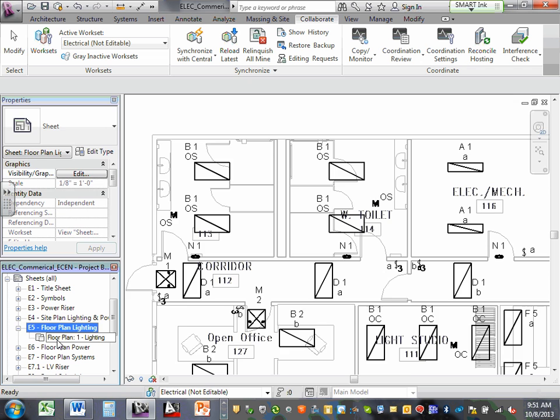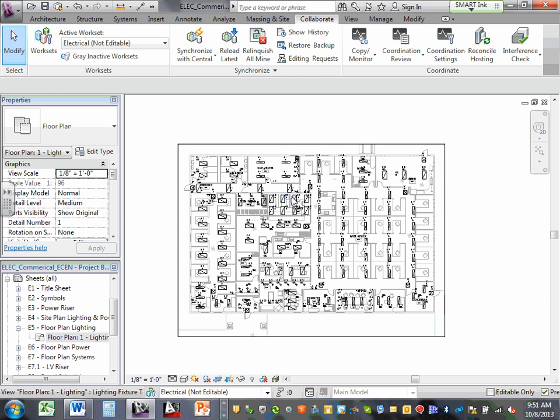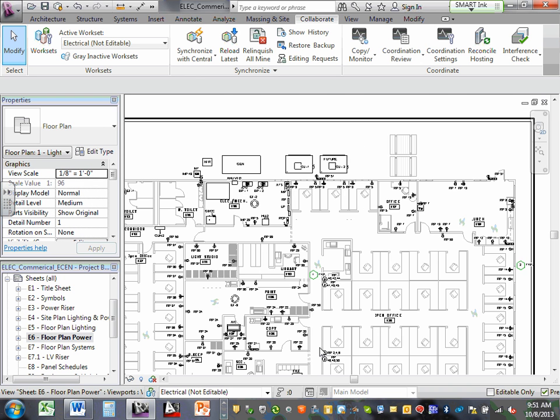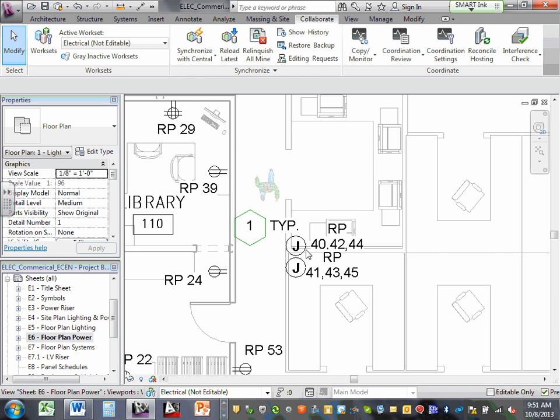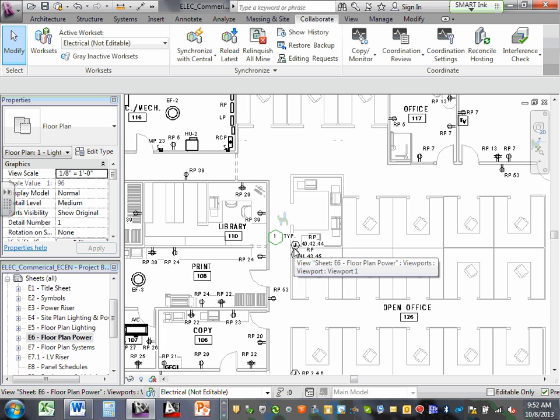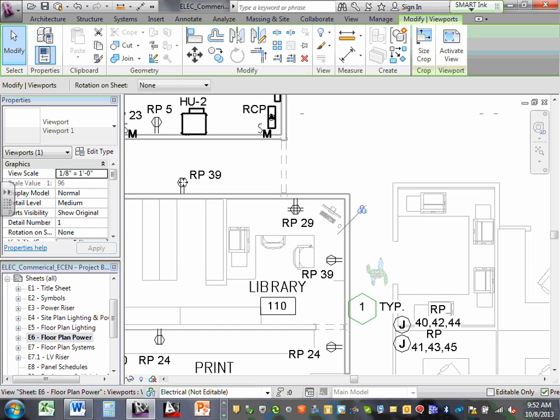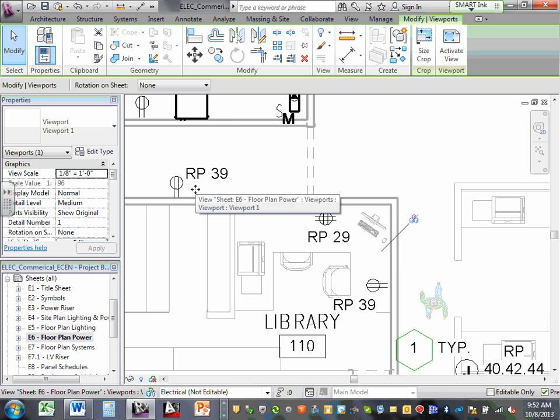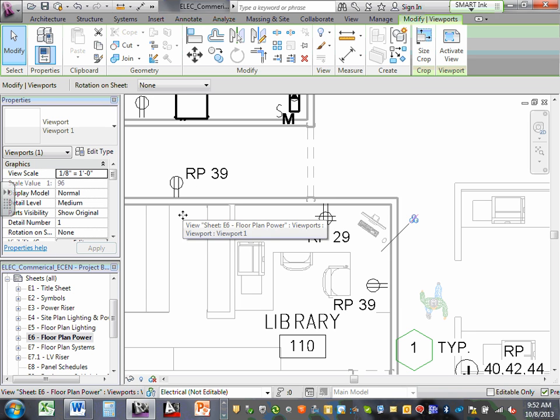Here's a floor plan — floor plan 1 lighting. Here's the power layout — for example, there's a J-box here with three circuits coming to it. Here's a receptacle. Right next to it is a tag — we're going to start tagging. The tag says RP, receptacle panel 39 — that's circuit 39 from the receptacle panel feeding this receptacle. See how easy that is?